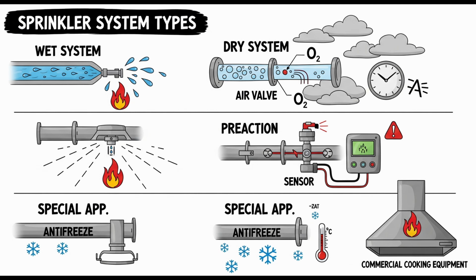It is. Now, there's a particularly strict rule for dry pipe systems protecting dwelling unit portions. Like if an apartment building or hotel has unheated areas, say an attic or crawl space, protected by dry pipe? Yes, exactly. For any dry pipe system protecting dwelling unit areas, the initial water discharge from the system test connection must occur in not more than 15 seconds. 15 seconds? That's way faster than the general 60-second rule. It is, much faster. And these systems protecting dwelling units cannot use the 500 or 750-gallon volume exemptions. They must meet that 15-second time limit, demonstrated either through calculation or testing. Wow. Why so much stricter for dwellings?